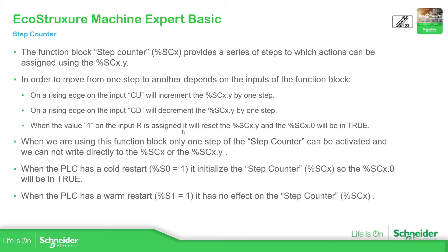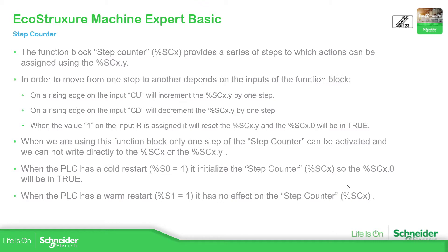Something that we need to know is that we cannot directly write into the step that we are in, and depending on how the restart of the controller works, we can lose the step that we are on. If we use a cold restart using %S0 it will lose the information on the step counter, and if we use a warm start it doesn't affect the counter.